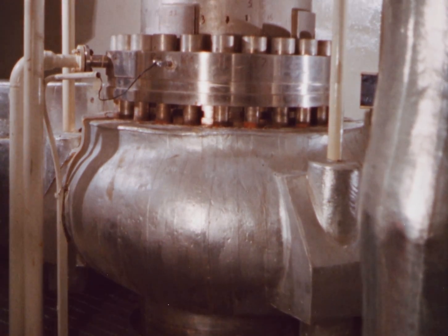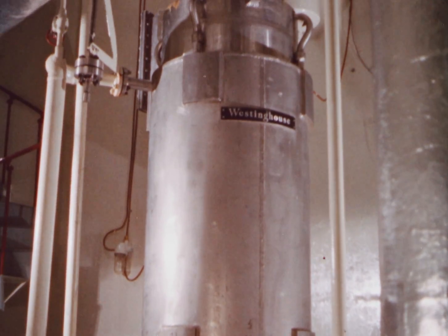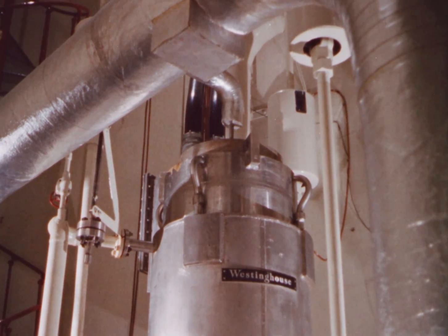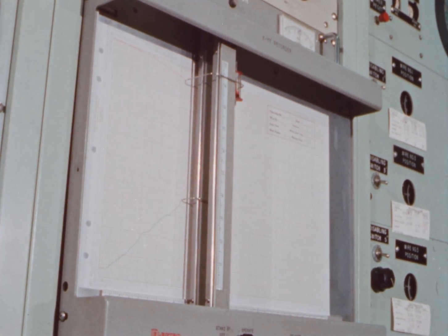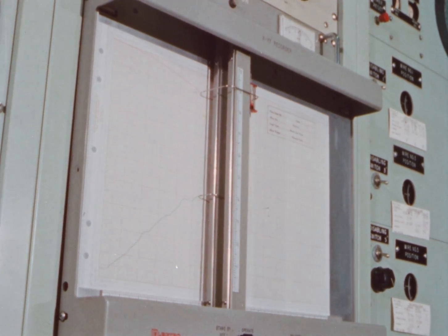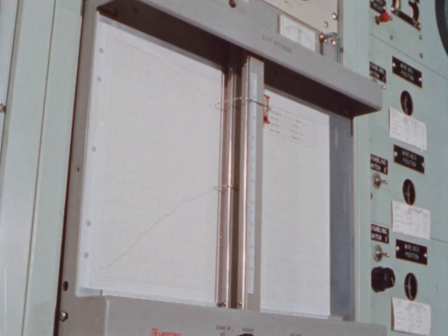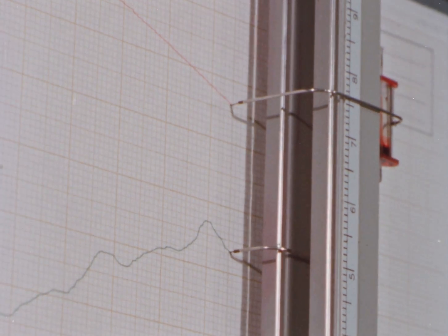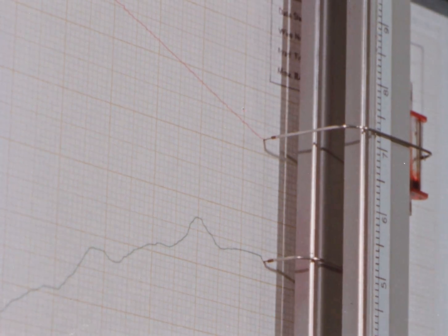Among Yankee's other novel features is the addition of boron to the coolant water to reduce reactivity during shutdown. And an in-core instrumentation system for monitoring reactor core performance, which also provides automatic readout in the control room. This system indicates start-up rate and flux level for all power ranges and provides shutdown signals should core power become too high.